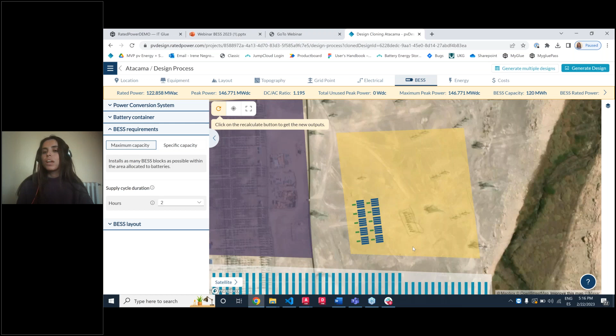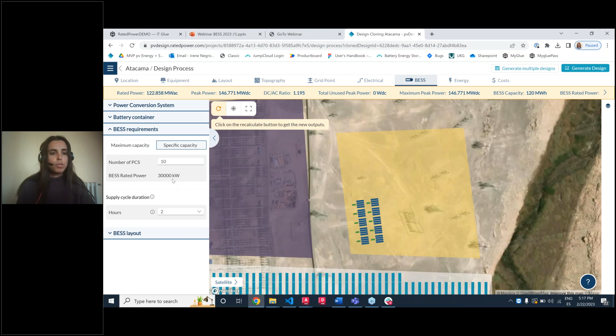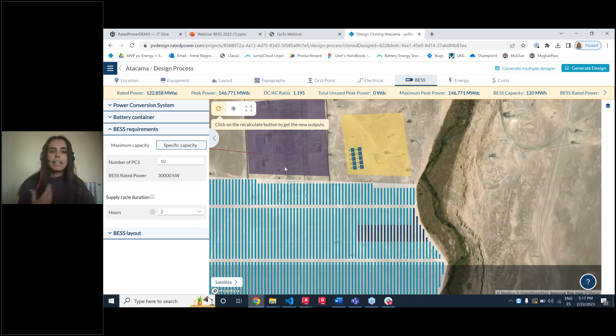In this case, as we have a specific size for our PV plant and know the specific peak power and rated power, it's better to manually specify the capacity of our battery. We just need to set the number of PCS, and the software will automatically set the power of our battery system — it could be 5%, 10%, or 15% of the total power of our PV plant. That depends on the size we want our battery to be, and also on the applications.